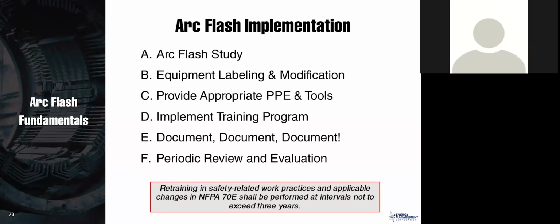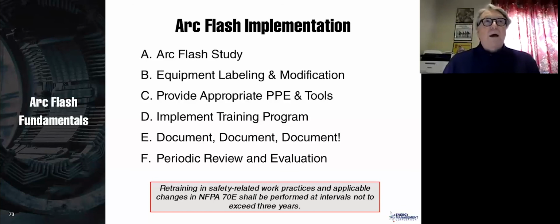Great. The next question is, if you have a breaker that is underrated for short circuit current, do you place a blast hazard label on the panel, and means to disconnect will have to be done upstream? No. Now, I kind of like the idea. I mean, if you put a label there that says, hey, there's something dangerous here, and you disconnect upstream, that's a good idea. But when you disconnect, typically there's not going to be a fault occurring. The problem is if there's a fault occurring at any time, that breaker could blow up and create a hazard. So if you have a breaker that's underrated, you have to change it. That's all there is to it.